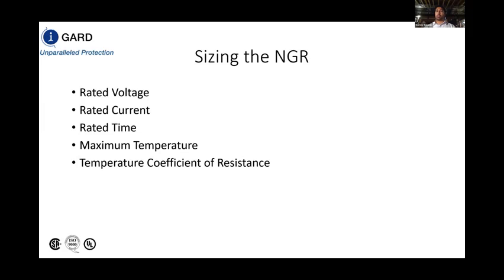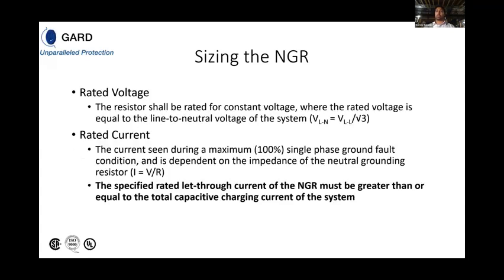For sizing of the NGR, there are 5 concepts to consider. That is rated voltage, rated current, rated time, the maximum temperature based on the time rating of the resistor, as well as the temperature coefficient of resistance for the particular alloy that is utilized in the construction of the resistor itself. With respect to rated voltage, it really depends on the type of system that you're specifying. For 13.8 kV generator, for example, we're insulating to the line to neutral voltage of the system. So in this case, we would be insulating the neutral grounding resistor to 8,000 volts line to neutral.